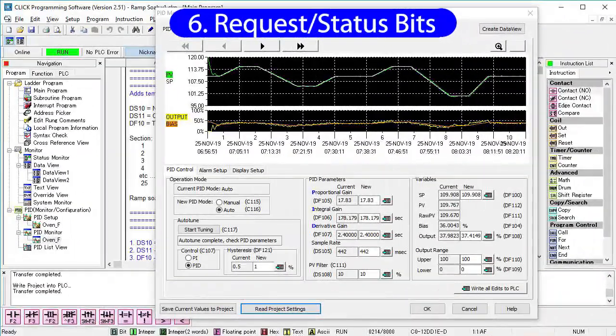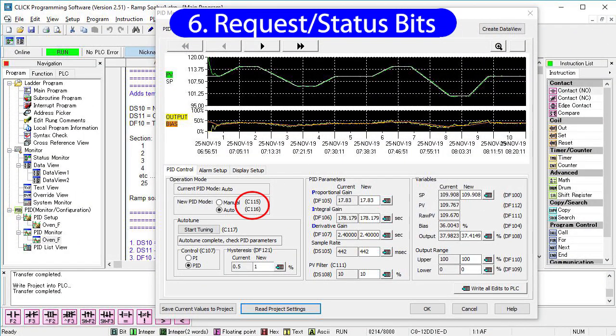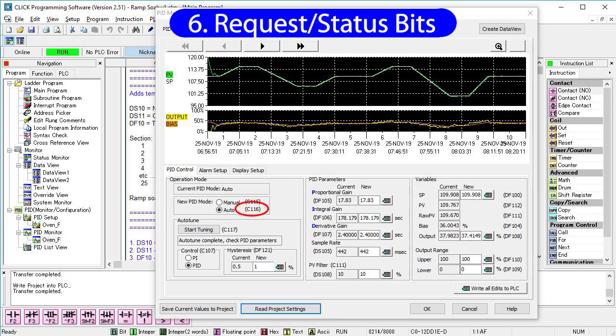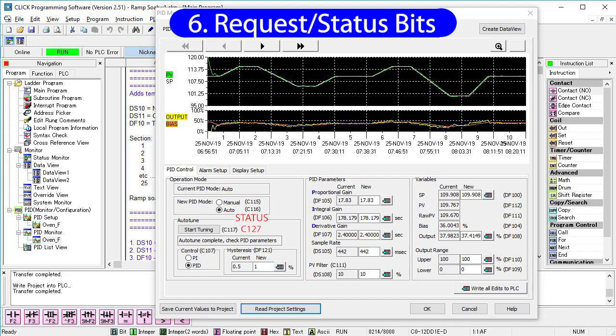Beware that these are not status bits. They don't tell you what the current mode is or if AutoTune is running. They are request bits. For example, if you want to switch to auto mode in your ladder code, you would set this bit. Once the transition has been made, PID will clear the bit so you know it's done. There are separate bits to indicate the actual status of these guys. Same thing for this one too.